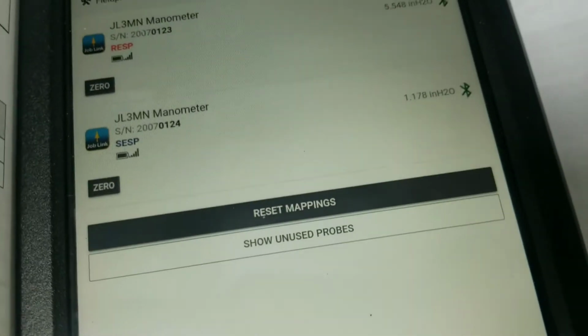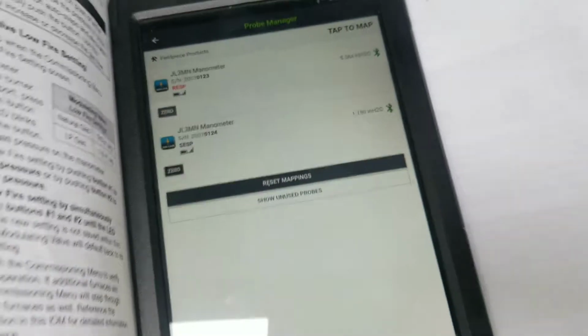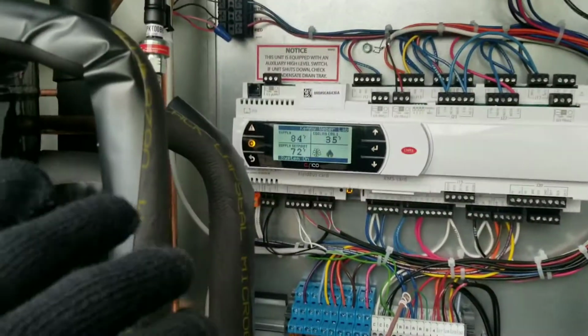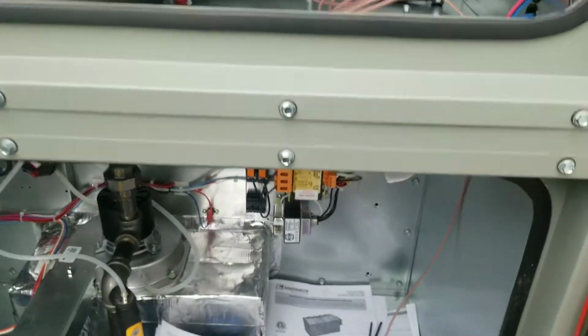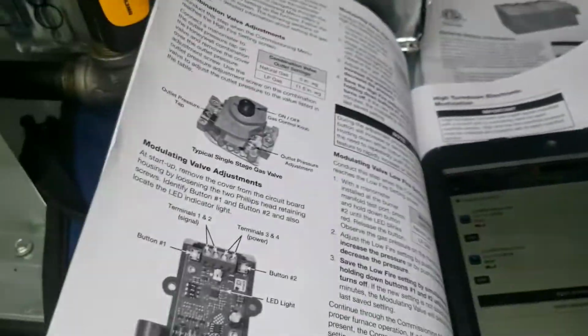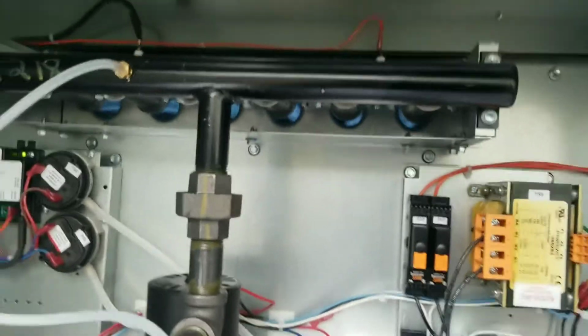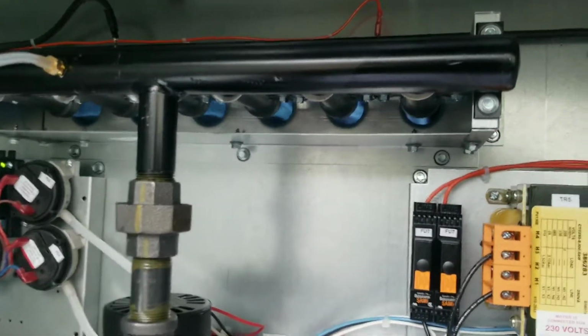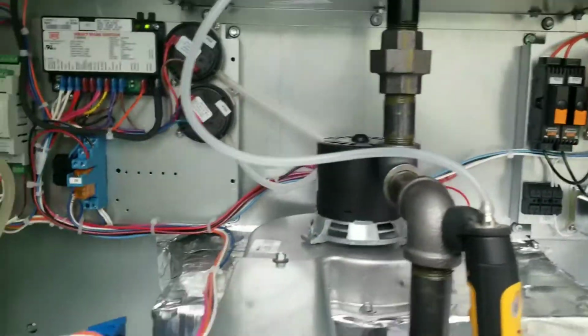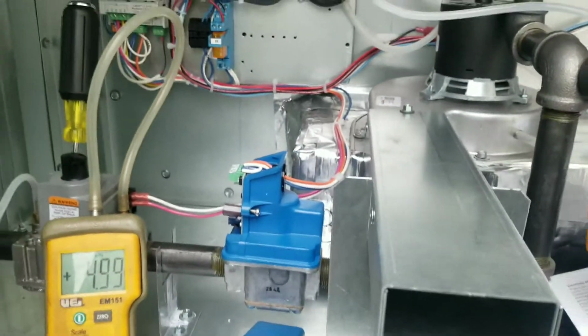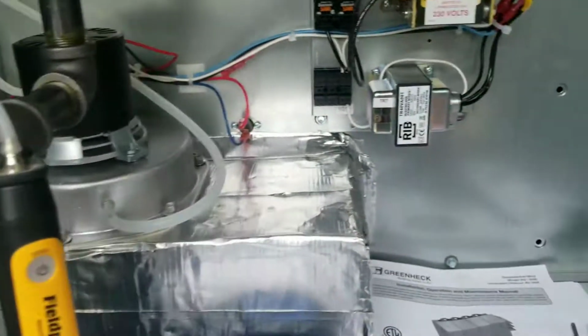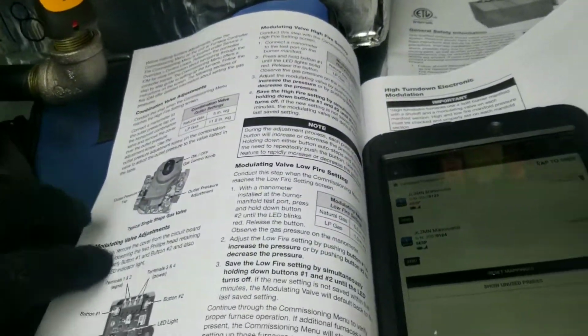We're at 1.1. 84 degrees. And we continue to drop. We're down to 1 inch now. It'll go down to 0.33 is the low fire setting. So this is kind of an interesting setup. It's not too bad once you know how to get in the control and do the commissioning and learn how to adjust that gas valve. That's an interesting adjustment with a little control board and buttons, but you gotta go through all your paperwork and adjust, and it gives you a step-by-step basically. But this guy's looking good.